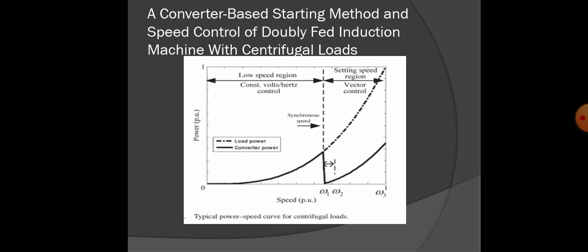And that is the typical power-speed curve for the centrifugal loads, where the x-axis is speed and the y-axis is power per unit, showing the load power and converter power. It is the low speed range with constant volts per frequency, and the right side is the setting speed region with vector control, that is, constant voltage by frequency control and vector speed control. We have the speeds omega 1 and omega 2, and omega 3 is the peak value, and the line starts from 0, and the speed is in between that.